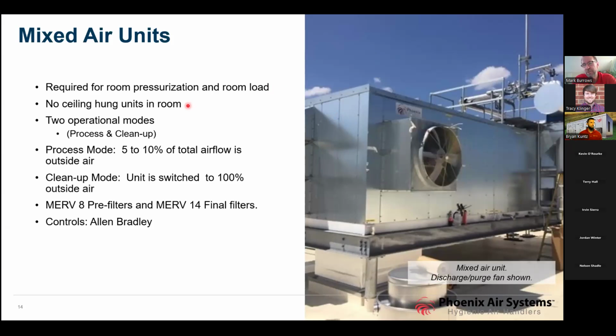In the picture to the right, we can do all kinds of things. This happens to be a bottom return. So it goes up and then into the unit. We can do bottom discharge. We can do end. The sky's the limit as far as what that looks like. 2 modes of operation again, process and cleanup, 5 to 10% outside air for process. Cleanup mode, 100%. The norm for these are the MERV 8 or a 30% pre-filter, which is the 2-inch throwaway.